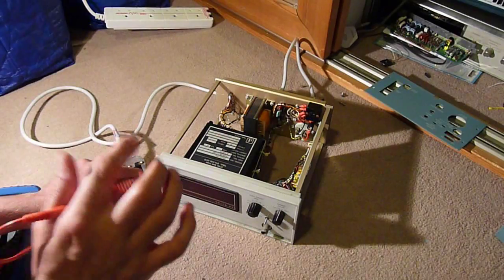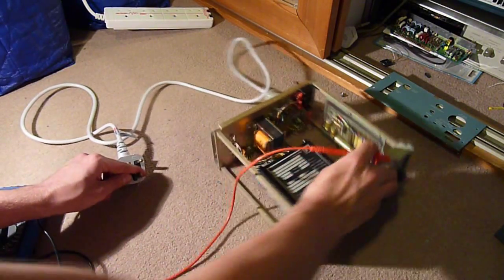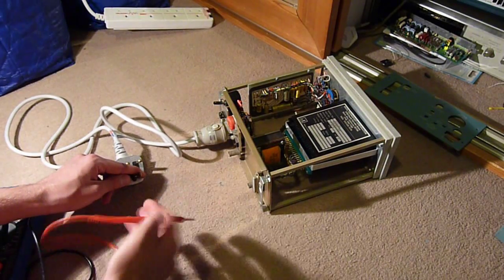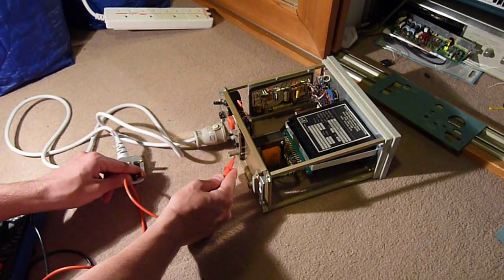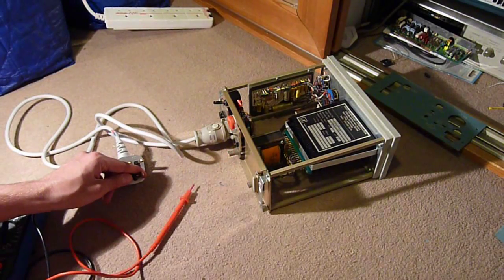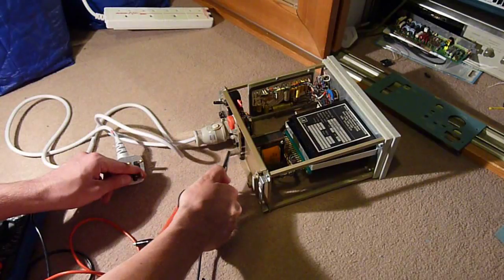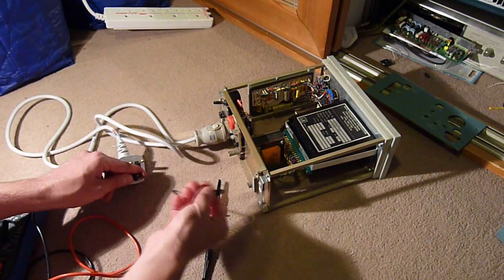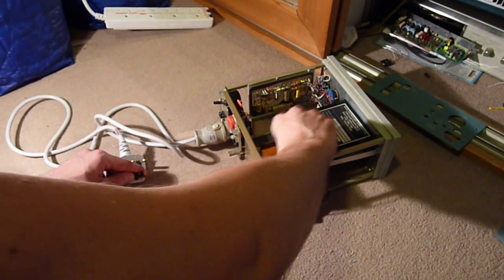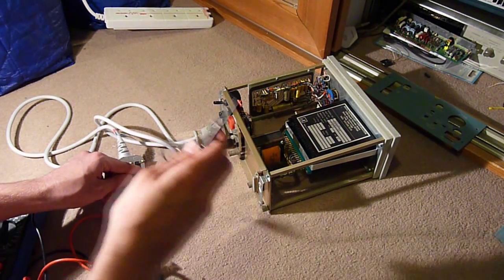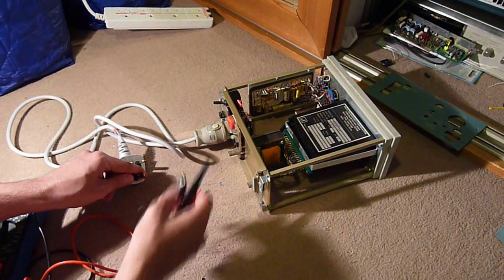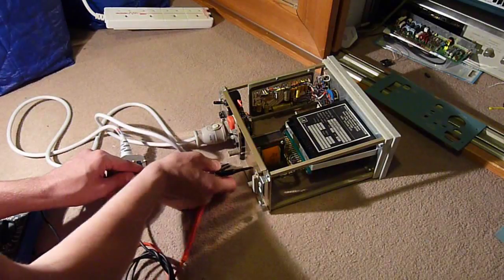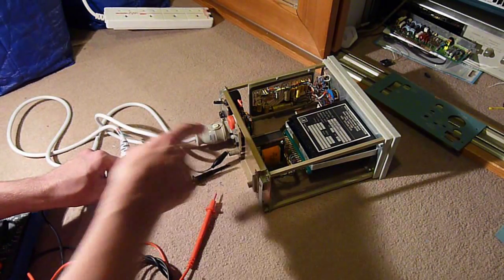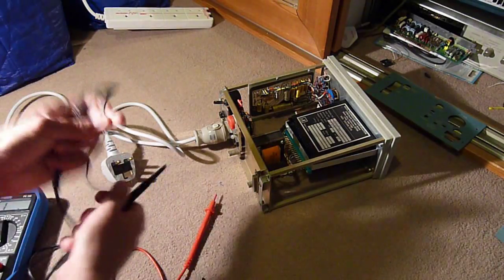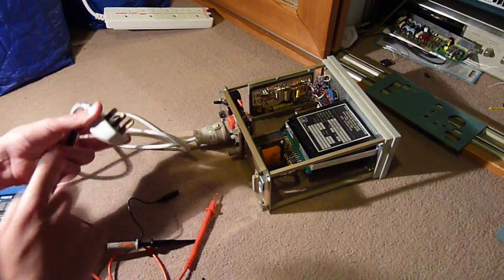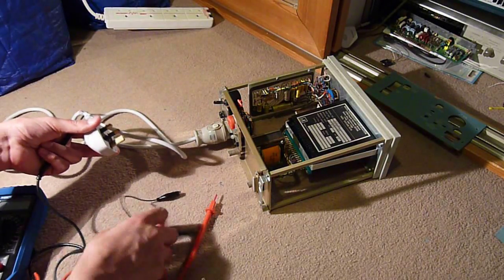Which essentially means, if you're measuring, such as, so you're testing this particular connector, do not connect this part of the probe to there, and then this to a positive part of the circuit, such as there. You will short circuit it and it will go bang. Connect only the negative, which in the scope itself is actually connected, because in the scopes themselves these are actually connected to the earth. So you can see how it causes a short circuit now, can't you? Well, I hope you can.